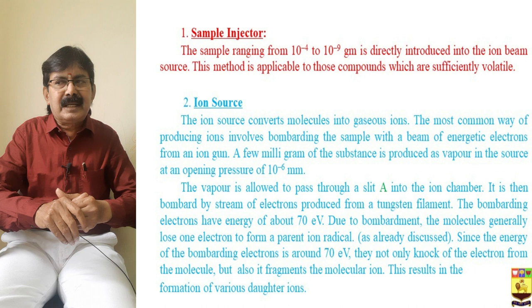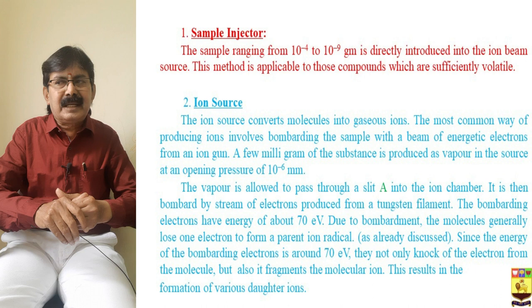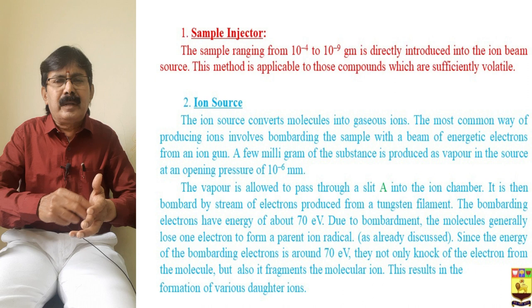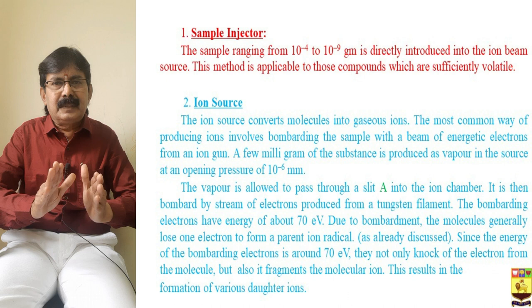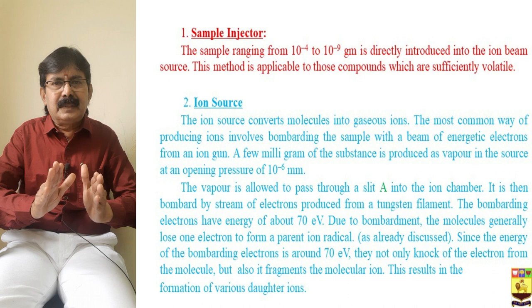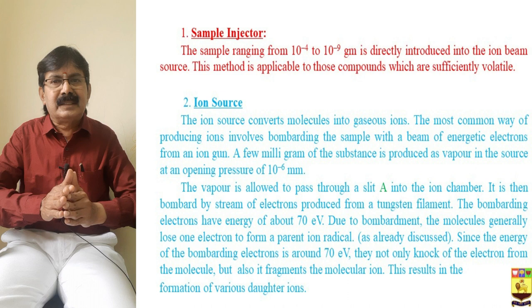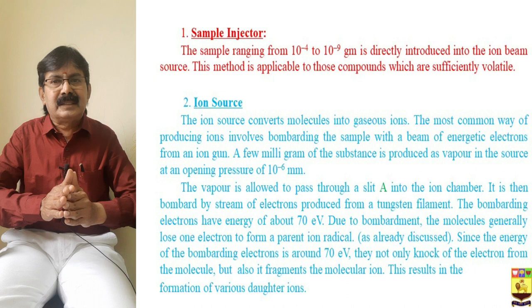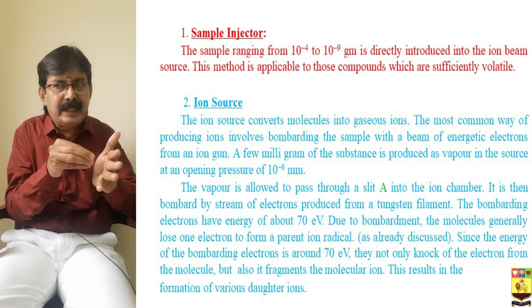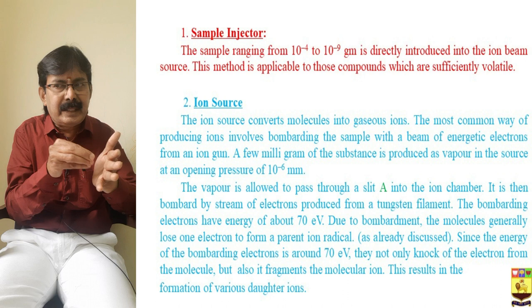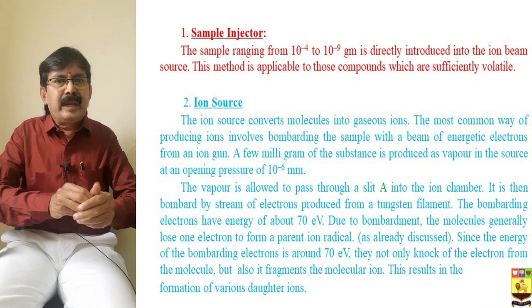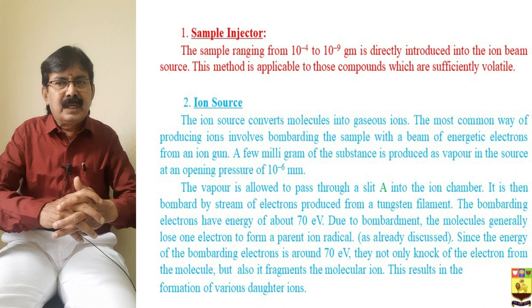The sample ranging from 10⁻⁴ to 10⁻⁹ grams is directly introduced into the ion beam source. This method is applicable for compounds that are sufficiently volatile, soluble, and highly volatile — the main condition is that the molecules must be in the gaseous phase. The ion source converts a molecule into gaseous ions. A few milligrams of substance is produced as vapor in the source at an operating pressure of 10⁻⁶ mmHg.